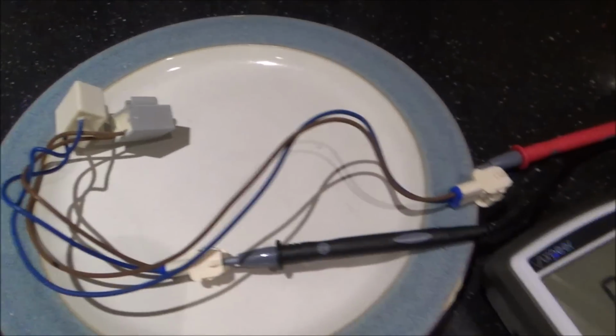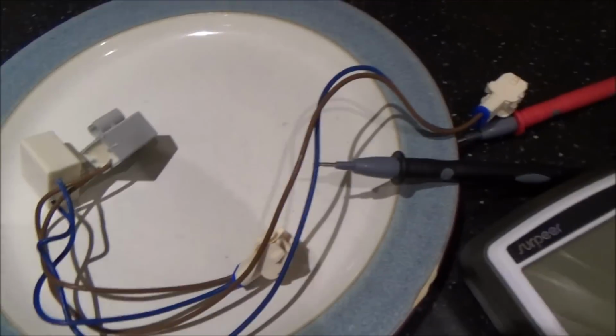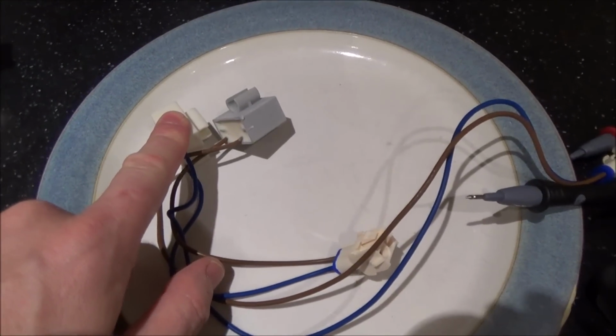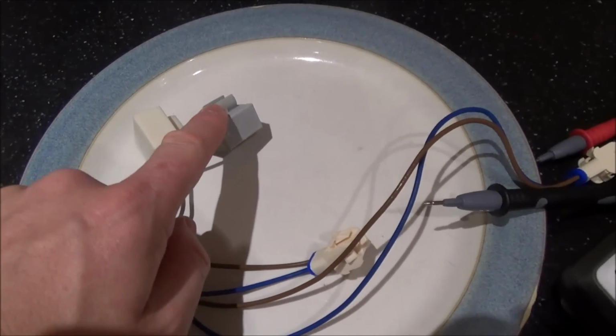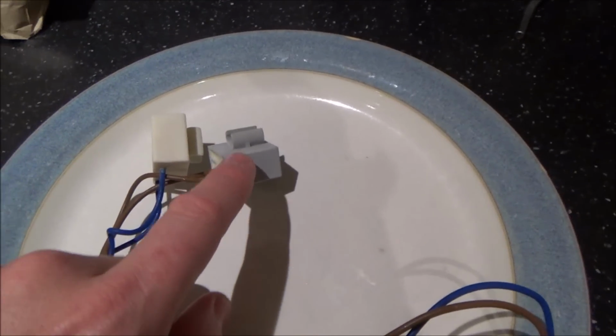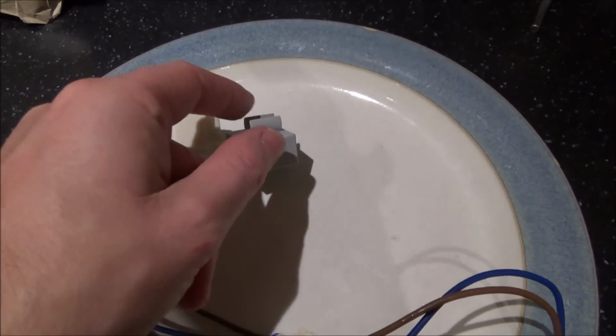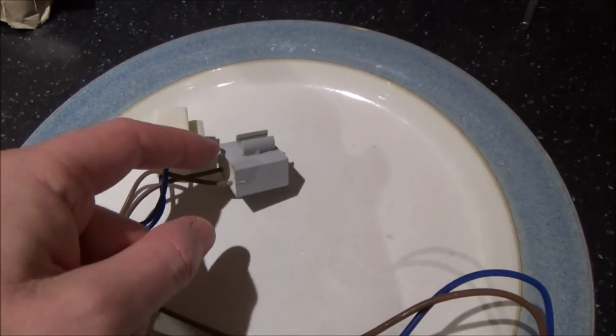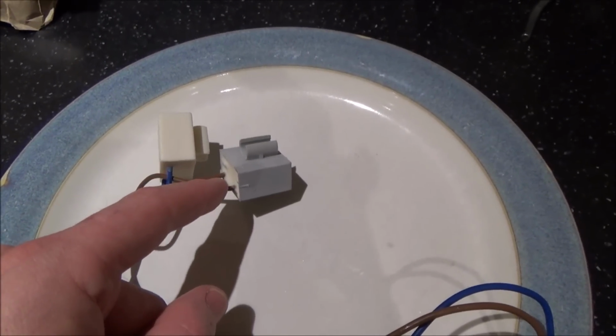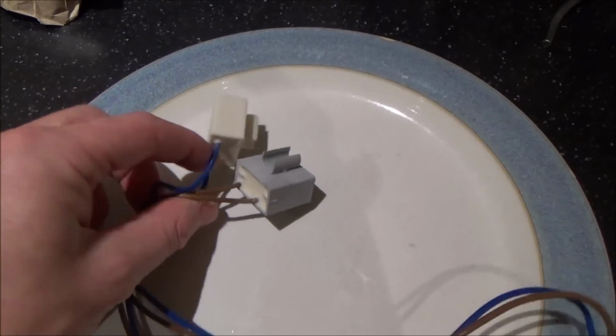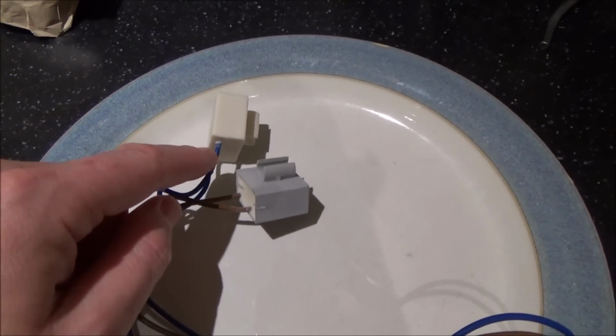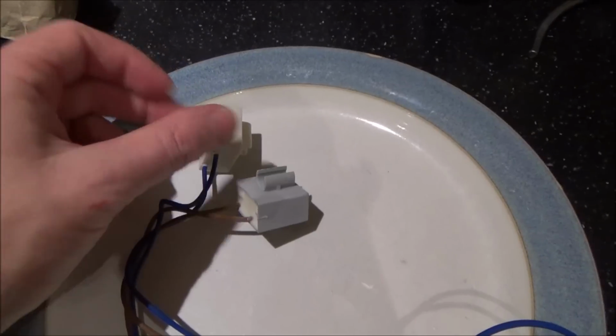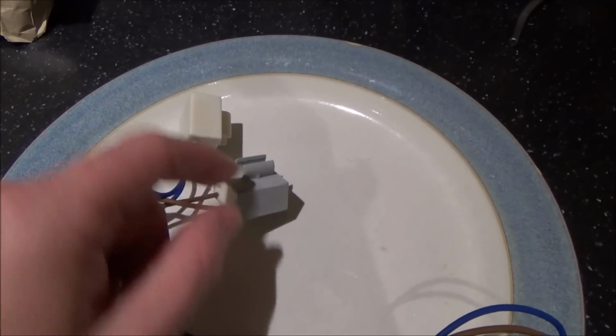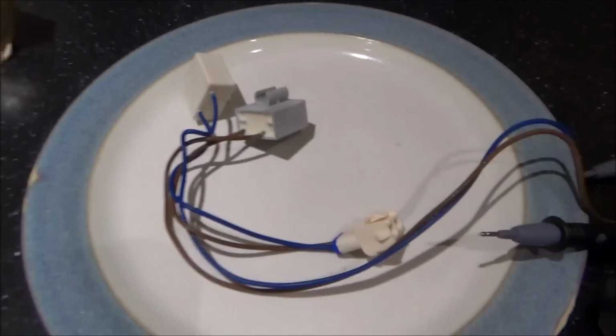Yeah, so, okay, just shows you knowledge is everything. This one here is the plus 40 degrees one, and this is the plus 8. So anything below plus 8 degrees C, there will be continuity here - in other words, it's joining both wires together. And anything below 40 degrees C, there's continuity on the blue wires. So once we go over 40 degrees C, this one breaks, and once we go over 8 degrees C, this one breaks. So now, bit by bit, as this warms up, it will stop beeping. Let me just put the wires back in.